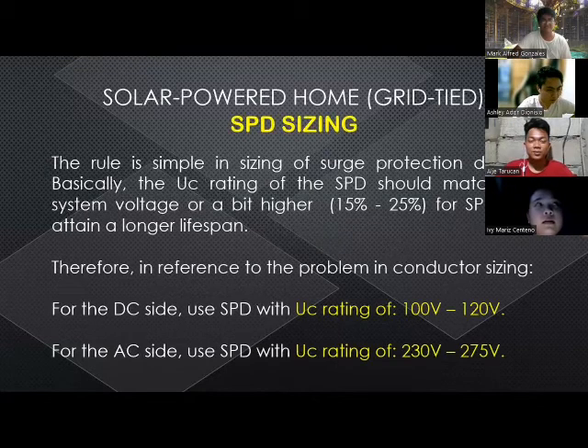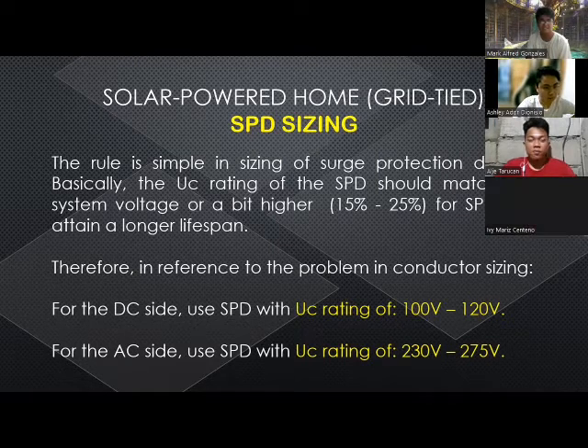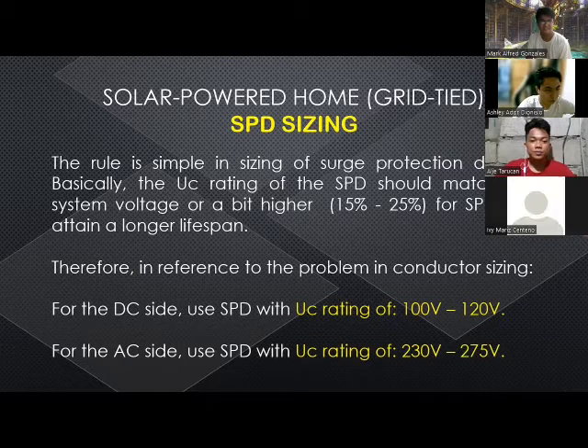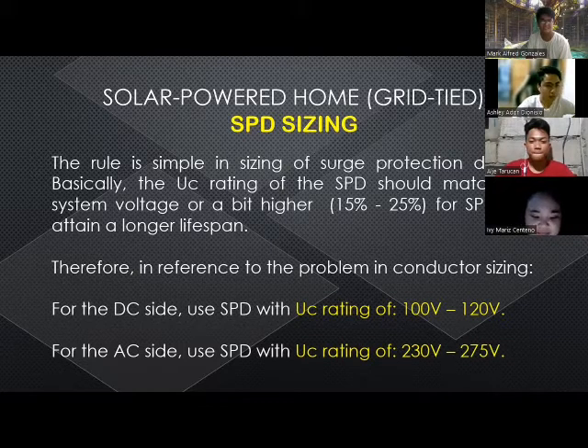Next is solar-powered home grid-tied surge protection device sizing. The rule is simple in sizing a surge protection device. Basically, the UC rating of the SPD should match the system voltage or be a bit higher, 15% to 25%, for SPDs to attain a longer lifespan. Therefore, in reference to the problem in conductor sizing, for the DC side, use an SPD with a UC rating of 100 volts to 120 volts. And for the AC side, use an SPD with a UC rating of 230 volts and 275 volts.